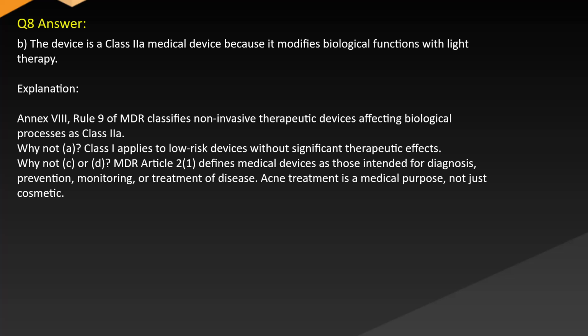Answer. B. The device is a Class IIa medical device because it modifies biological functions with light therapy. Explanation. Annex VIII, Rule 9 of MDR classifies non-invasive therapeutic devices affecting biological processes as Class IIa. Why not A? Class I applies to low-risk devices without significant therapeutic effects. Why not C or D? MDR Article 2(1) defines medical devices as those intended for diagnosis, prevention, monitoring, or treatment of disease. Acne treatment is a medical purpose, not just cosmetic.